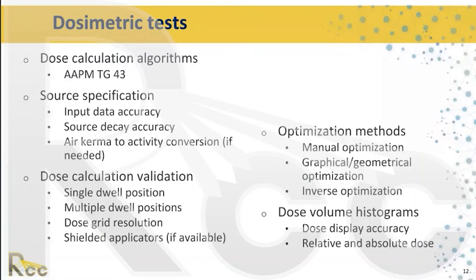Now moving to dosimetric tests. Most participants are likely familiar with the AAPM TG-43 formalism for brachytherapy dose calculations — that report is freely available and I encourage everyone to download and read it. It is the formalism followed across the United States and mostly Canada. It covers source specification, accuracy of input data, source decay, air kerma strength, activity conversion, dose calculation validation, optimization methods, and DVHs.